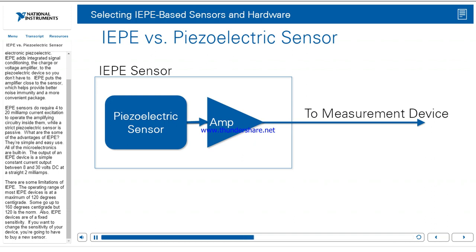What are some of the advantages of IEPE? They're simple and easy to use — all of the microelectronics are built in. The output of an IEPE device is a simple constant current output between 8 and 30 volts DC at 2 milliamps. There are some limitations: the operating range of most IEPE devices is a maximum of 120 degrees centigrade, some go up to 160 degrees, but 120 is the norm. Also, IEPE devices are of a fixed sensitivity — if you want to change the sensitivity, you're going to have to buy a new sensor.